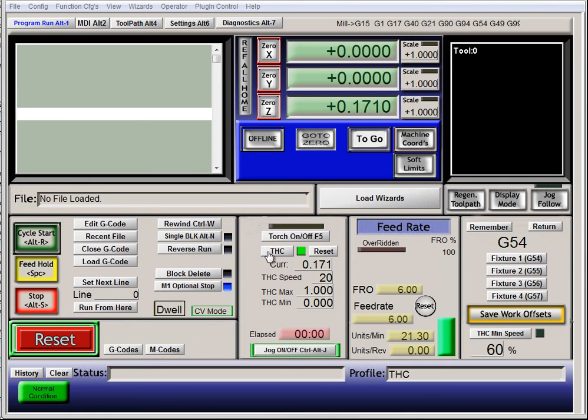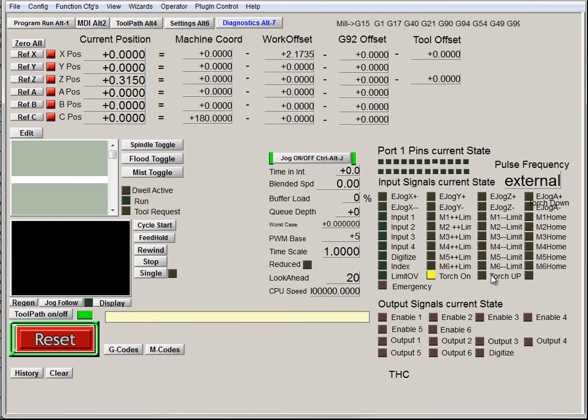If I turn off THC, it stops responding to them, even though the torch up and torch down signals are still turning on and off.